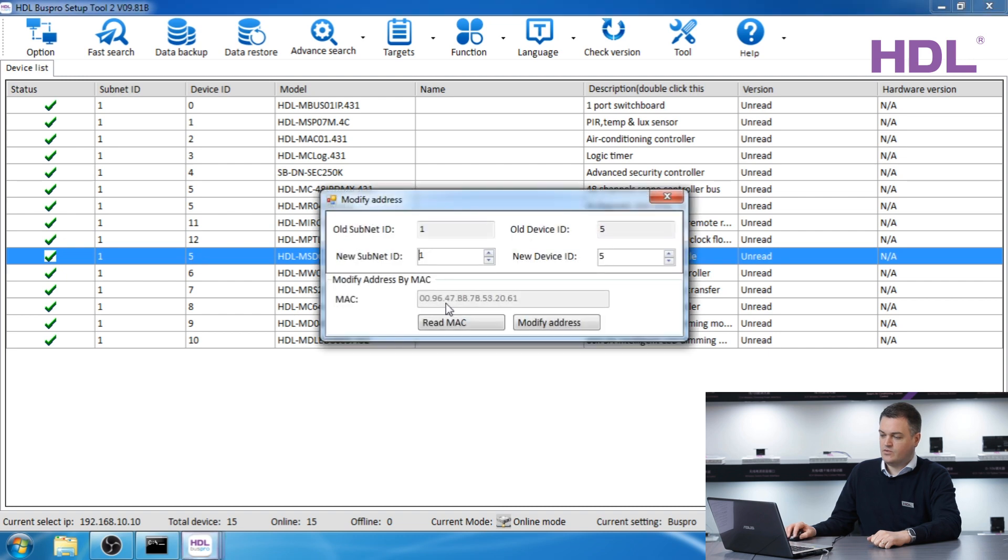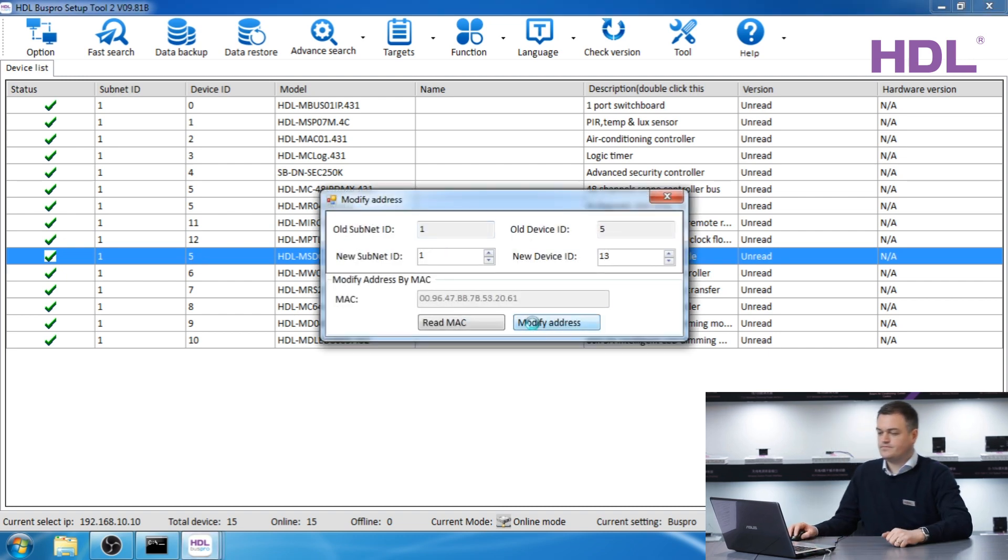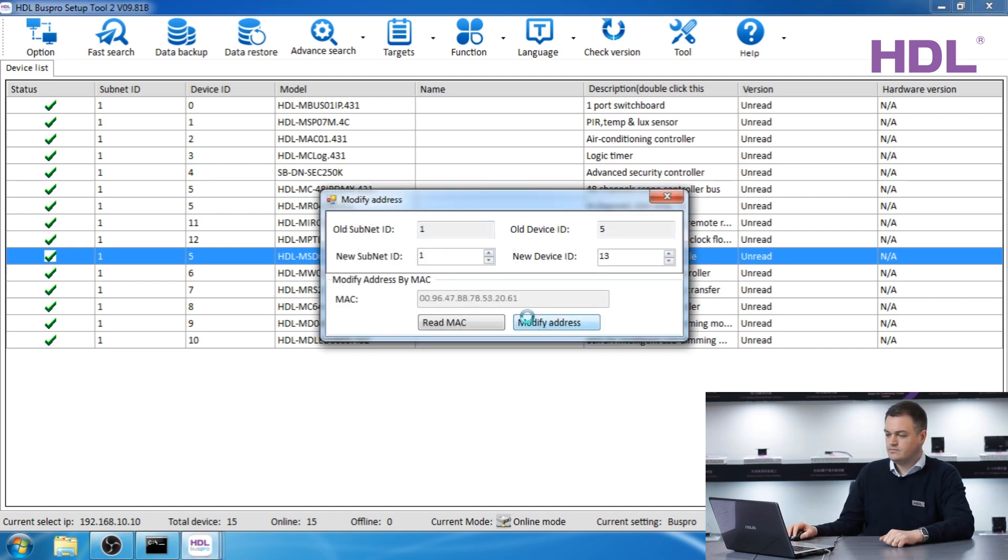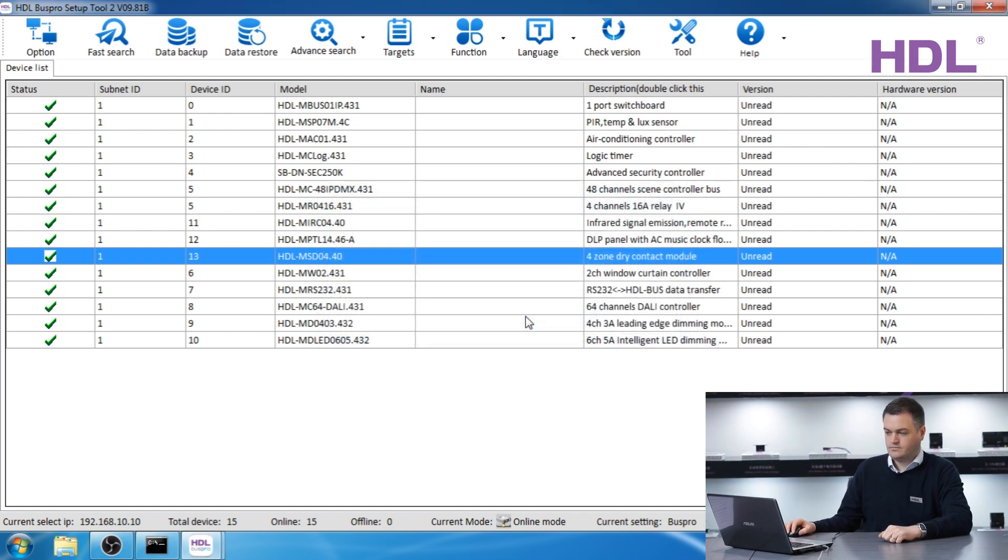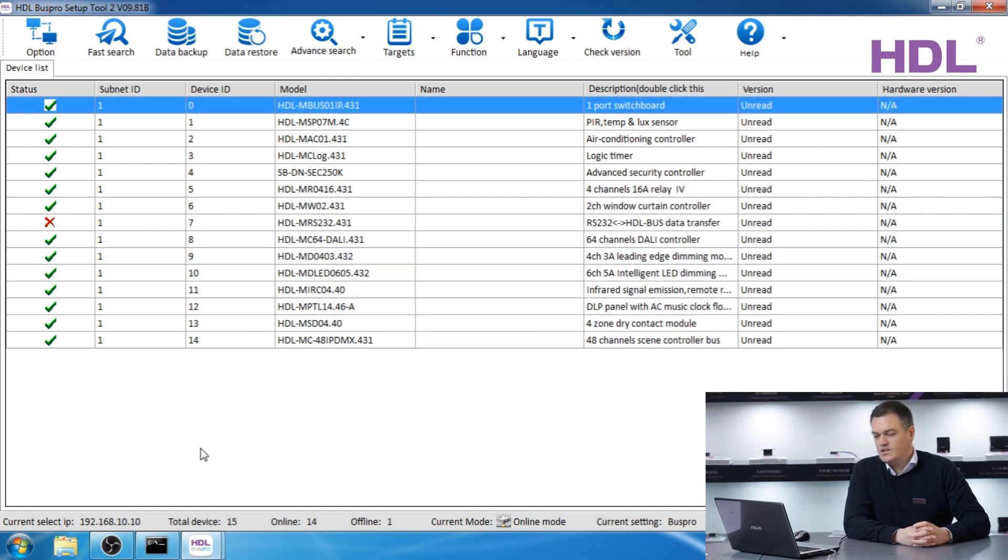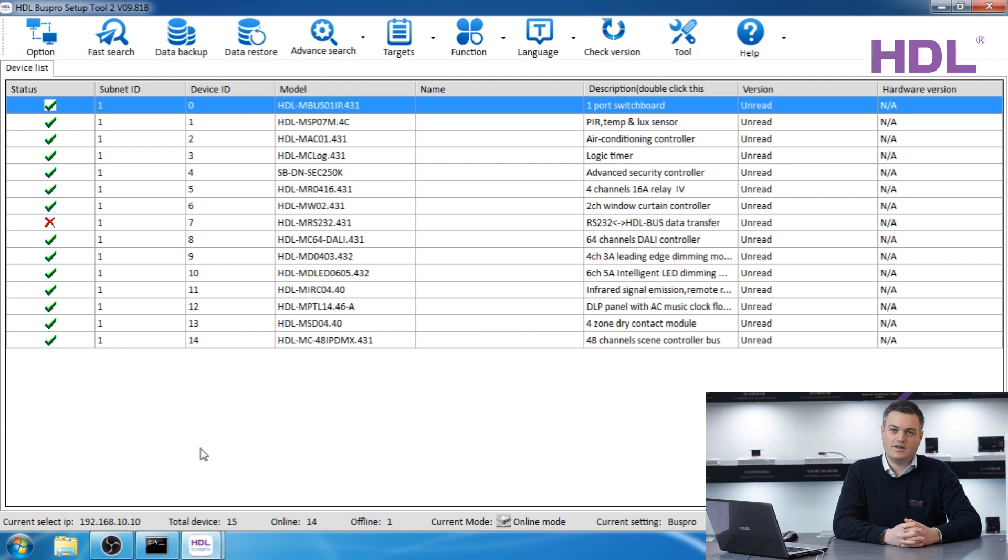Let's press fast search to bring the rest of the devices because there are some keypads and some sensors and other modules we want to check. We have no devices with the same address because every device should have a unique address between 1 and 254. Here is an infrared module so I'm going to change this to 11.